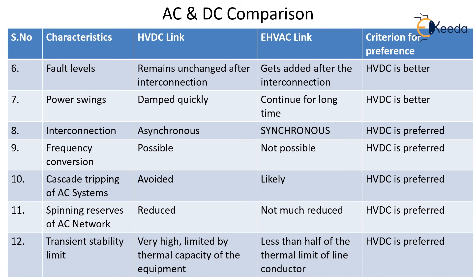Finally, for transient stability limit, HVDC has a very high transient stability limit, limited only by the thermal capacity of the equipment. In contrast, the EHVAC transient stability limit is less than half of the thermal limit of the line conductor. Across all these factors we can justify that HVDC links are comparatively better than EHVAC links.